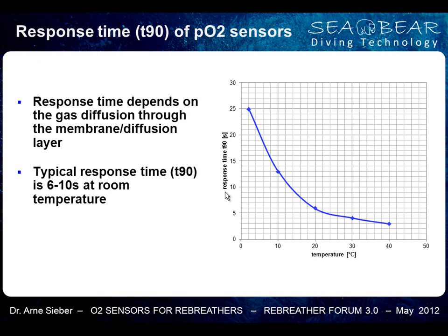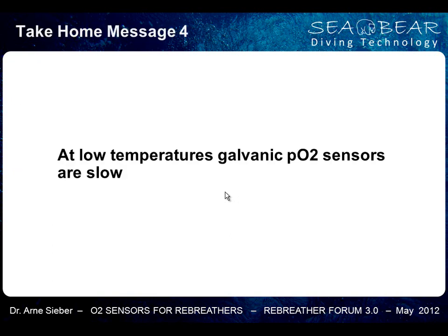And this takes time, and it's very strongly temperature dependent. If you do the calculations, you'll see that at room temperature the sensor might have a response time of 6 seconds. If it's even warmer, it will go down maybe to 3 seconds. But what happens if you go close to 0 degrees? The response time will rise, and it can go up to 25 seconds, for example. So keep this in mind when you want to do a calibration or something like this. If the galvanic sensors are very cold, their response time is very slow.